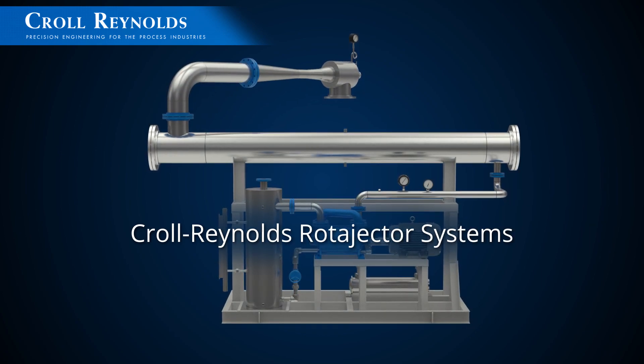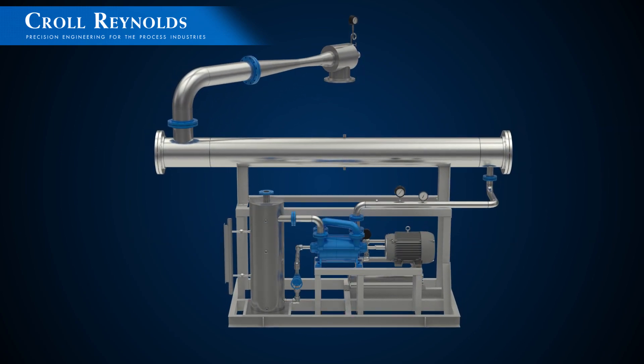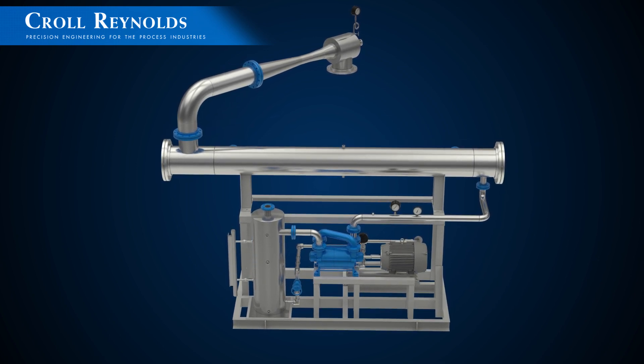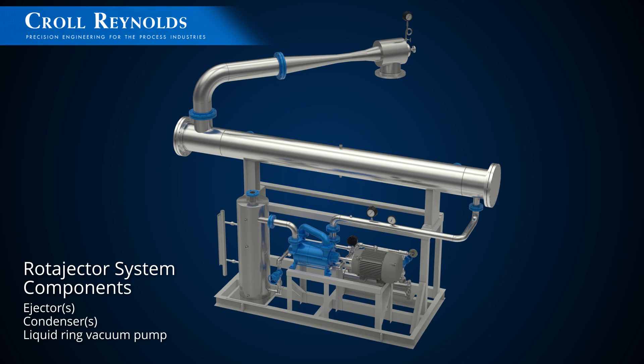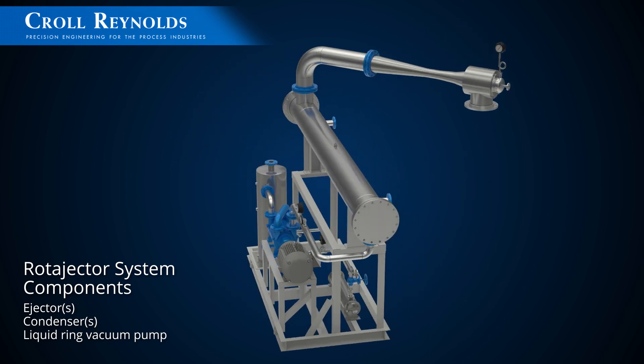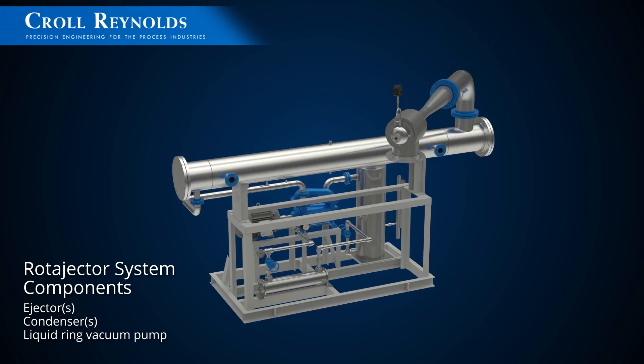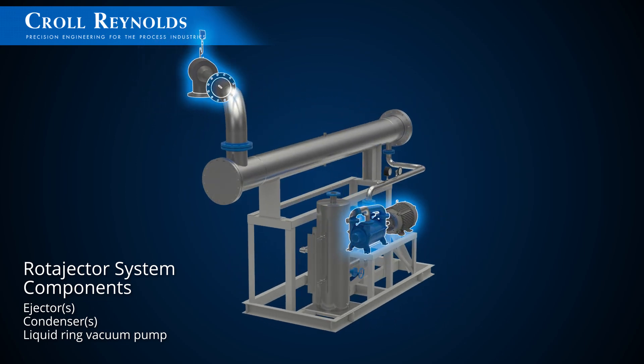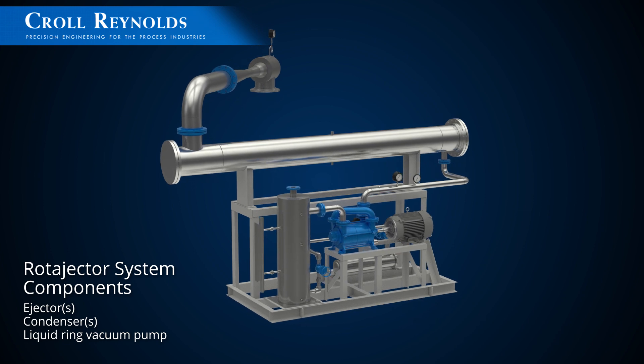Rotajector systems were developed by Croll Reynolds vacuum engineers in the 1970s to address rising energy costs. Rotajector systems are high-efficiency combination ejector liquid ring vacuum pump systems, wherein the liquid ring pump replaces the final ejector stage of the system to reduce steam consumption.